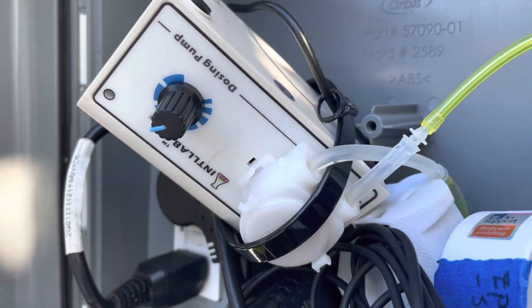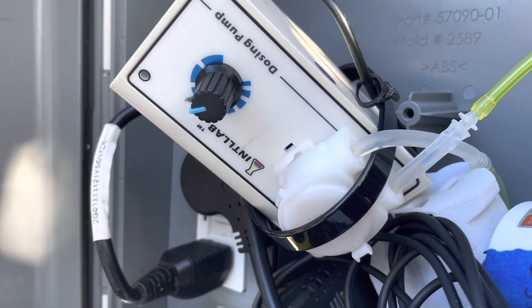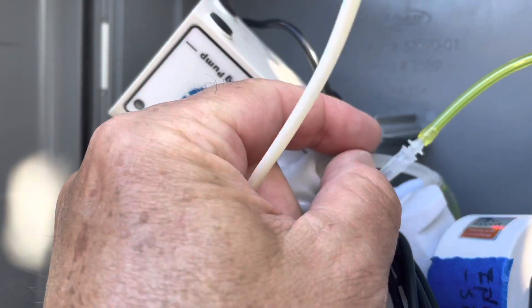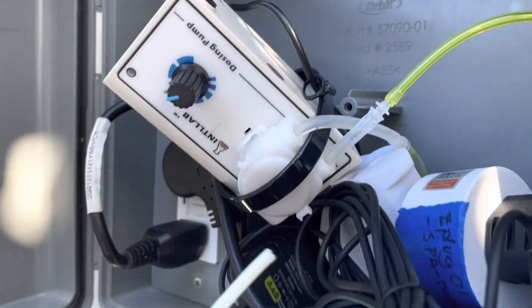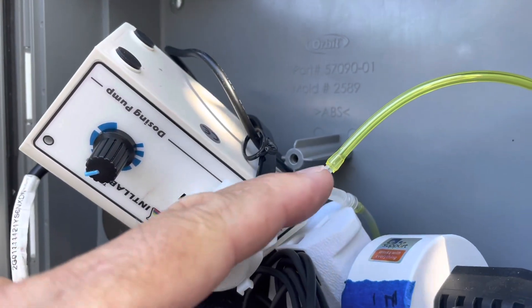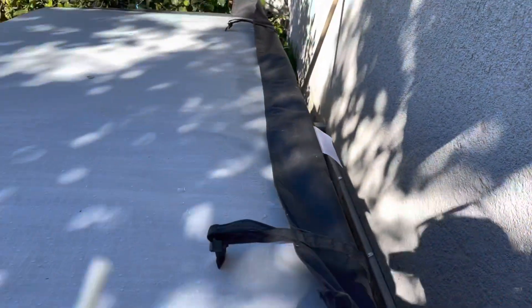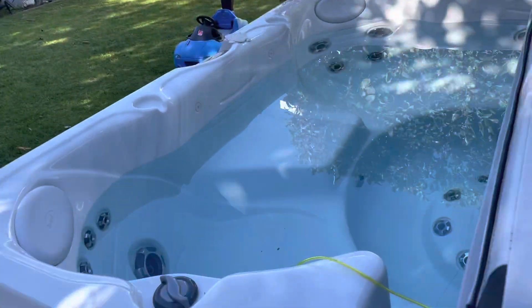The pump has a problem with the head coming off. I put a tie wrap around it and that seems to fix the problem. For the first few months this head kept popping off, but now it doesn't come off anymore. I just put Tygon sleeving on that and it's happy.